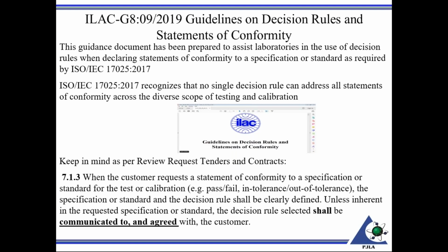Keep in mind with your decision rule, and I have a copy there, I have documented there 7.1.3. When I'm doing an assessment, decision rule comes up in two places. It comes up in 7.1.3 during contract review. So that's how you take measurement uncertainty into account. The decision rule, if you recall, that's a definition. And you see the requirement: the decision rule selected shall be communicated to and agreed to with the customer.